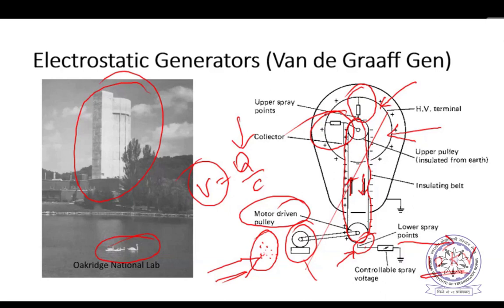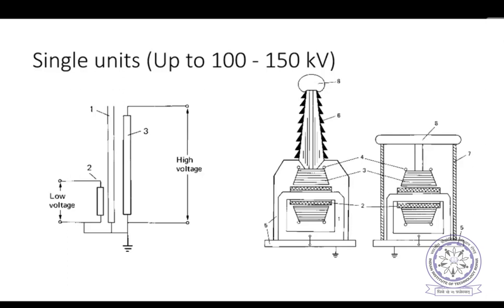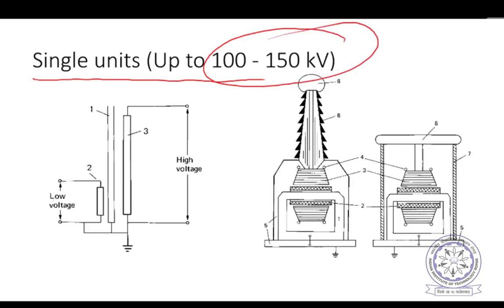Now, until now we have covered the DC voltages. Now alternating voltages. Alternating voltages are very simple to generate. Alternating voltage we already get in a laboratory, 230 volts AC. So in order to generate high voltage, what is to be done? Naturally we have to use transformers. That's what is actually done to generate high voltages in a laboratory. These are single units, and with this kind of construction, only around 100 to 150 kilovolts can be generated.